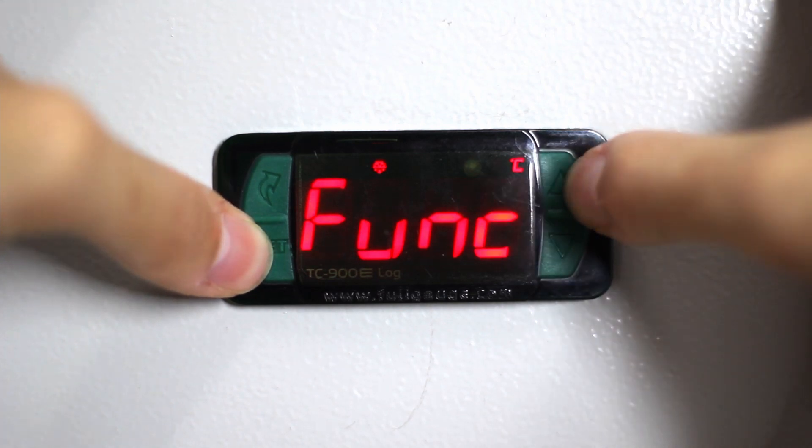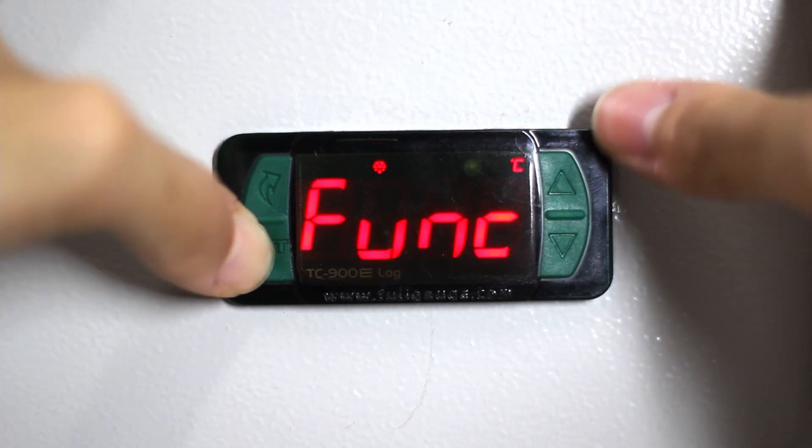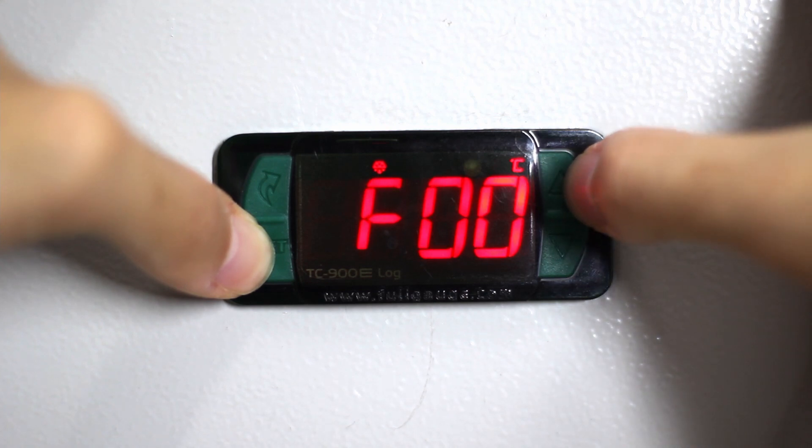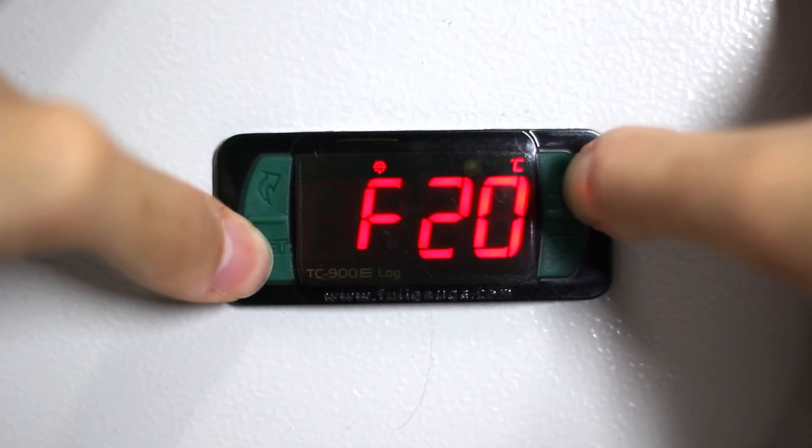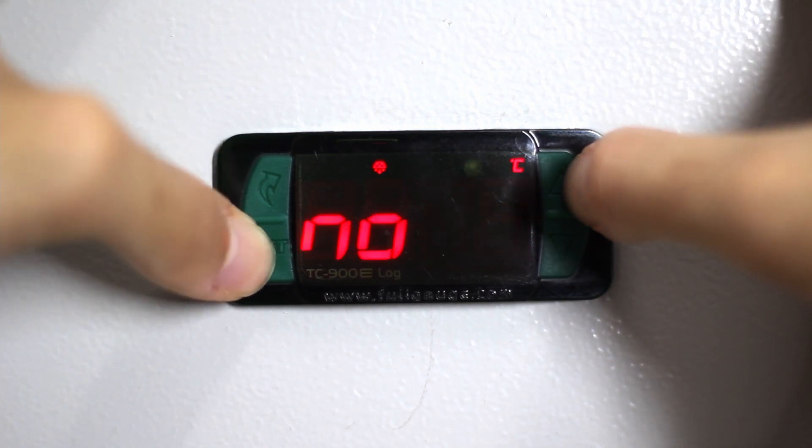Go to F00, press SET and enter value 1 to enable advanced function. Select now F37 to limit the hours in economy mode. This number is the time limit in hours that economic set point will remain activated.